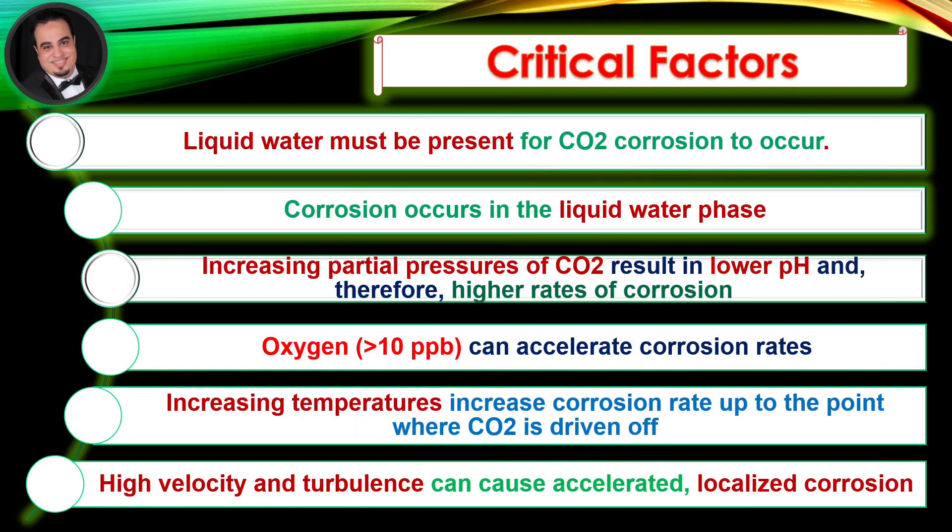Critical factors: Liquid water must be present for CO2 corrosion to occur; corrosion occurs in the liquid water phase. Increasing partial pressures of CO2 result in lower pH and therefore higher rates of corrosion.